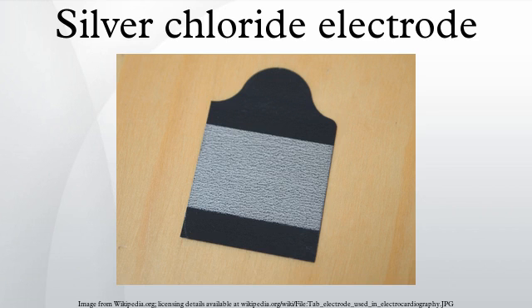A silver chloride electrode is a type of reference electrode, commonly used in electrochemical measurements. For example, it is usually the internal reference electrode in pH meters. As another example, the silver chloride electrode is the most commonly used reference electrode for testing cathodic protection corrosion control systems in seawater environments.